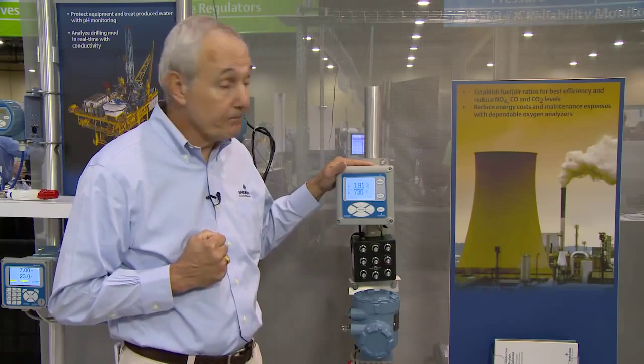If you're in a process that has high particulate matter, like a coal-fired boiler with fly ash, or a cement kiln, or a biofuels boiler with much particulate matter, this analyzer will diagnose when the filter on the end of the probe needs to be replaced.